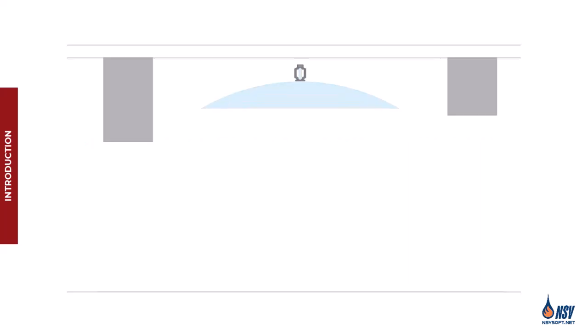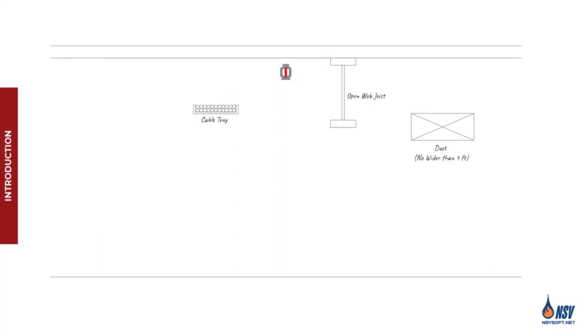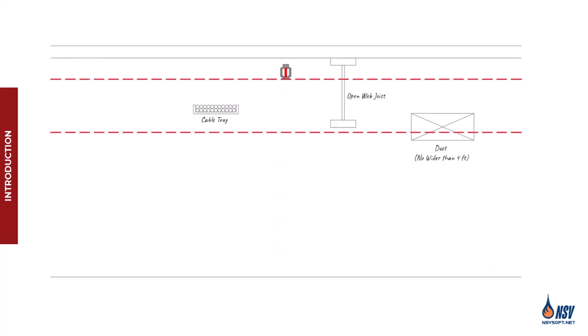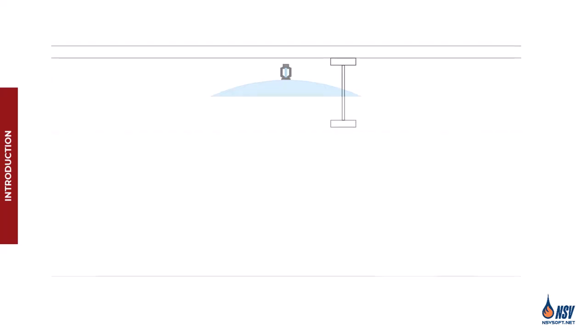In that video, we applied the beam rule to situations where the only available path for water was beneath the obstruction. Now we're shifting focus to cases where any part of the obstruction is located within 18 inches vertically from the deflector and water can pass on both sides of it.